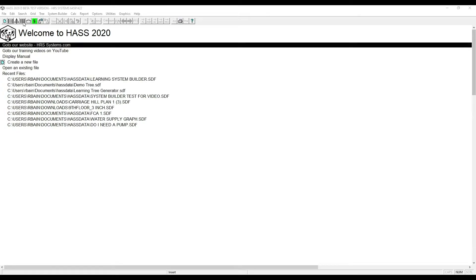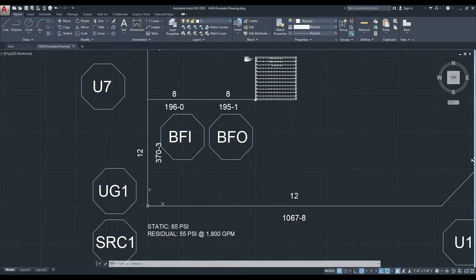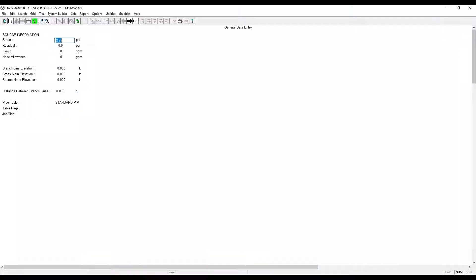To start, click on New System Builder. Now we need to enter the water supply information. For this example, we will be using a static of 65, residual of 55, flowing 1800.